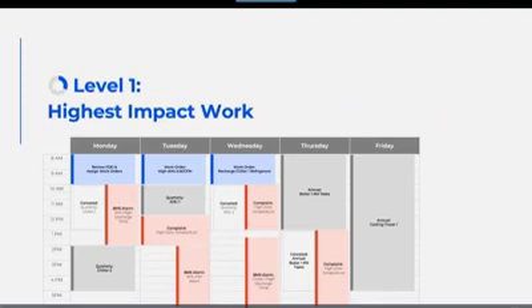To go back to the schedule approach we looked at, it got filled up with all this red, all these alarms. Here's what FDD can do, shown in blue. On Monday, they're reviewing the FDD tool and finding issues. That enables action: we can see an air handler where the amperage over time is increasing, a sign the fan motor might fail. So let's get ahead of that failure. On Tuesday, a technician does service on that critical air handling unit because we think it's going to fail.